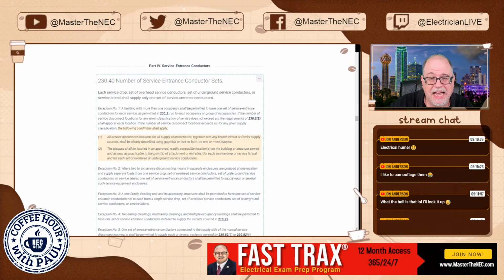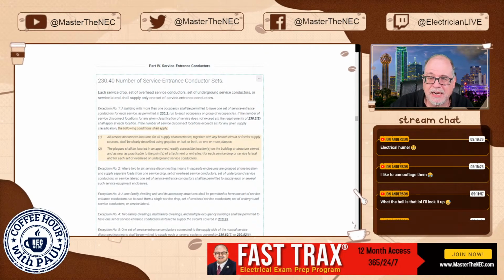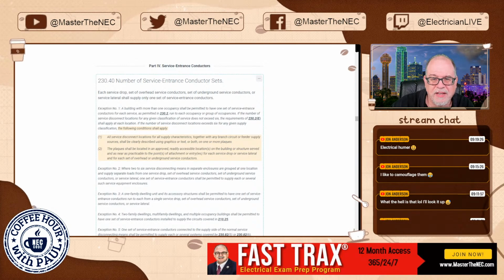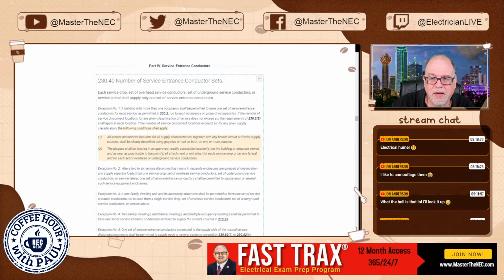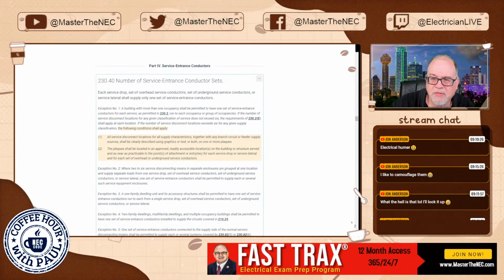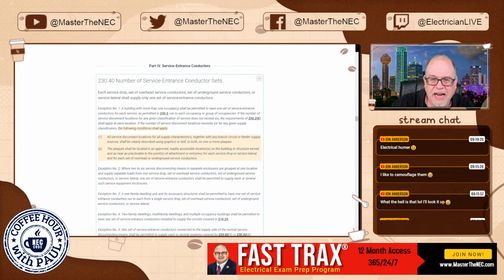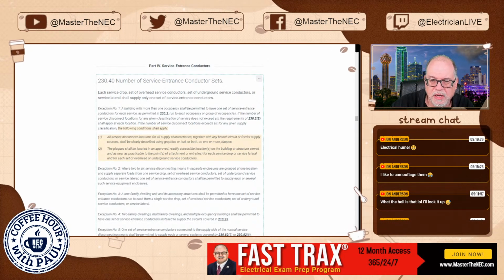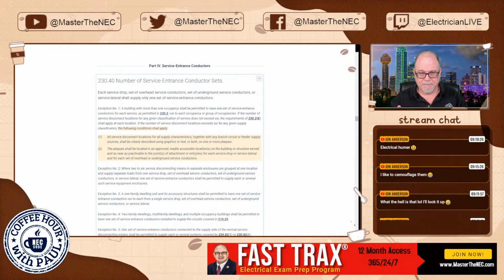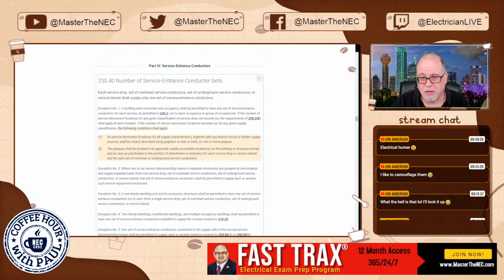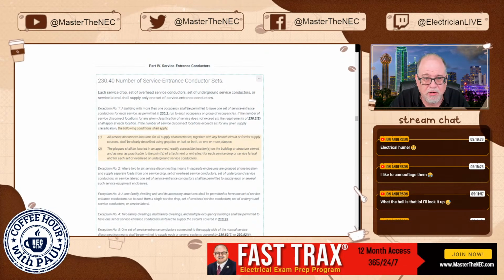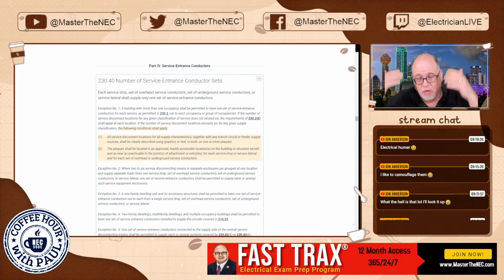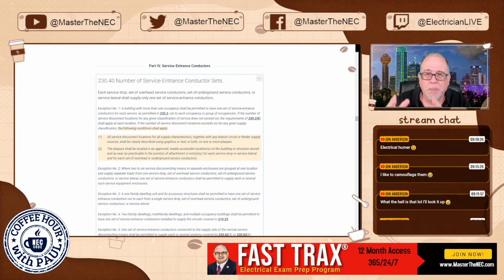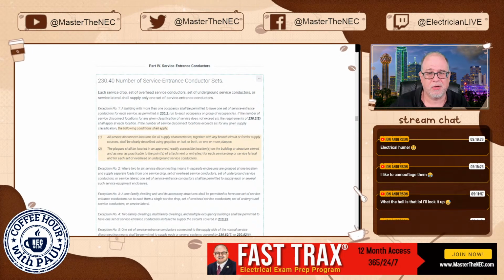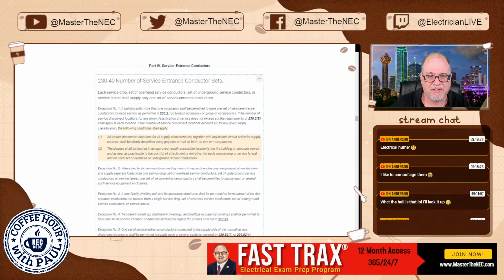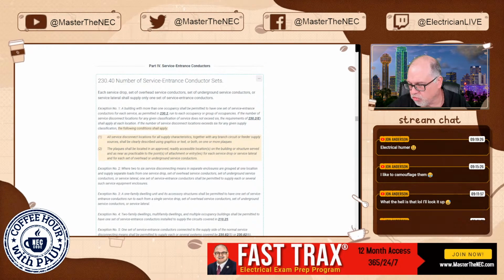And then (2), it says the plaques shall be located in an approved, readily accessible location on the building or structure served and as near as practicable to the point of attachment or entries for each service drop or service lateral and for each set of overhead or underground service conductors. So we want to make sure that we have this plaque, we would be approved, so the AHJ's got to be okay with where you do it, is readily accessible and as near as practical to the points of attachment from those service drops or those laterals where they come in. Okay, so you put this labeling there. Again, this is only going to apply when the number of service disconnects exceeds 6 for any given classification, right? So that's the rules there.